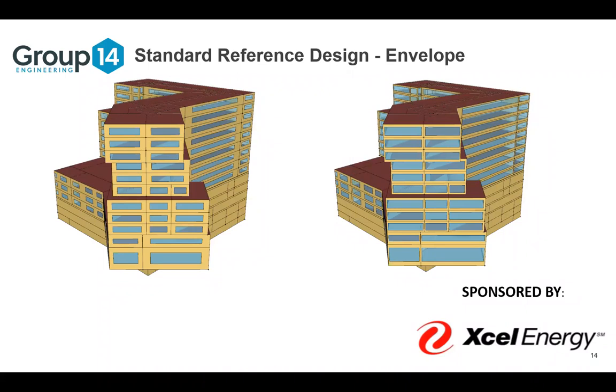This is an example of a multifamily building located in Denver that has a 65% window to wall ratio, and that's on the right side, so that's our proposed design. On the left side is the baseline design, and that has only that 40% window to wall ratio. So you can see that we took a big hit for that increased glazing. You can actually see the difference, how much glazing was modeled in both buildings.